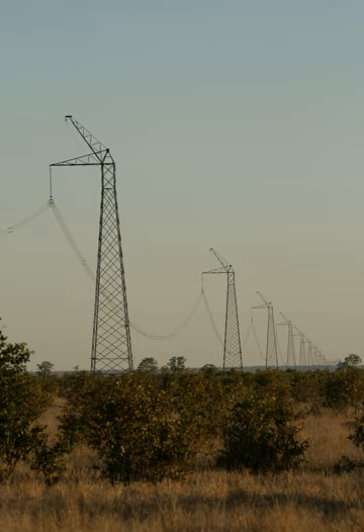In addition to New Zealand and Australia, single-wire earth return is used throughout the globe. In 1981, a high-power 8.5-mile prototype SWER line was successfully installed from a diesel plant in Bethel to Napakiak in Alaska, United States. It operates at 80 kV and was originally installed on special lightweight fiberglass poles that formed an A-frame. The A-framed poles could be carried on lightweight snow machines and installed with hand tools on permafrost without extensive digging, though erection of anchoring poles still required heavy machinery, with dramatic cost savings.